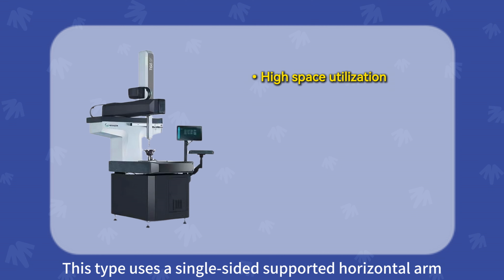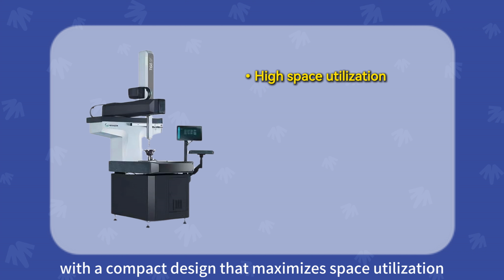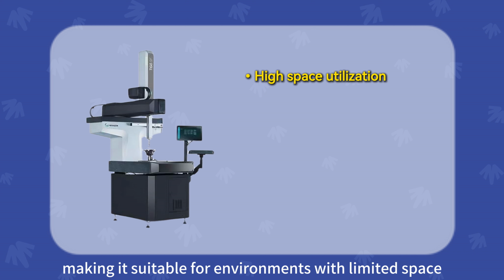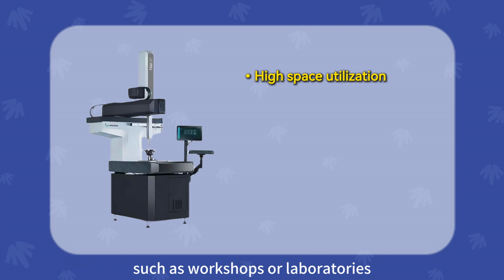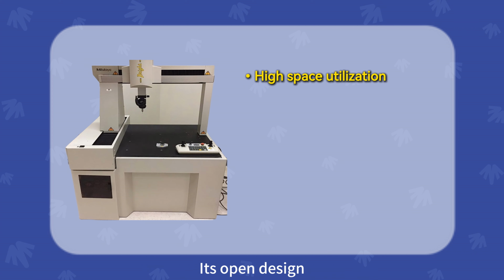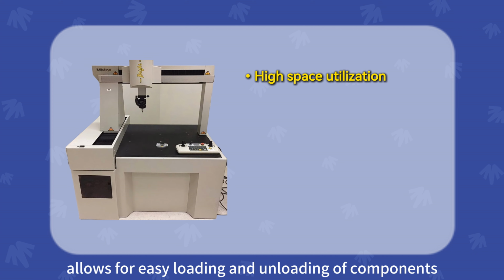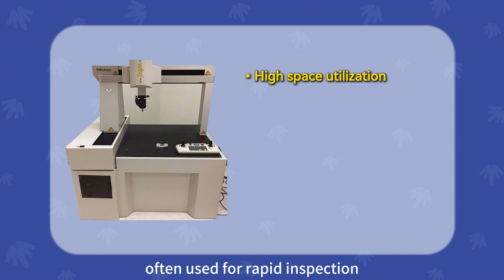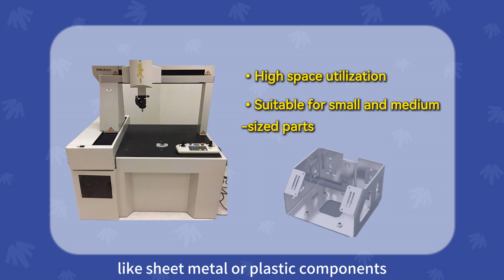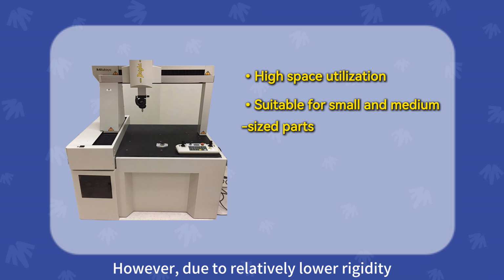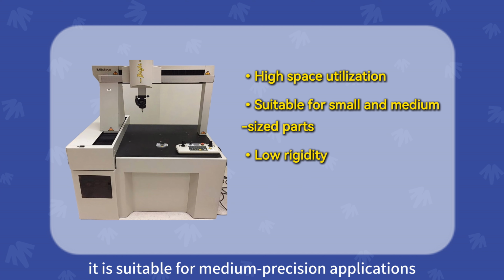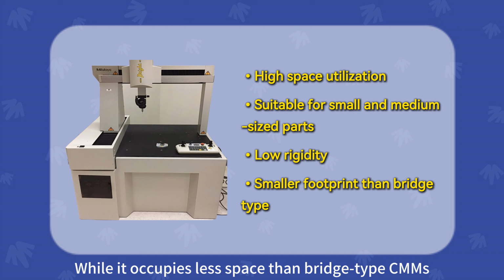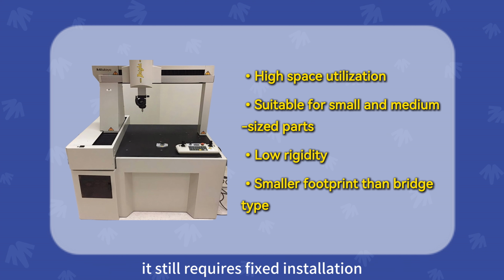Cantilever-Type CMM. This type uses a single-sided supported horizontal arm, with a compact design that maximizes space utilization, making it suitable for environments with limited space, such as workshops or laboratories. Its open design allows for easy loading and unloading of components, often used for rapid inspection of small to medium-sized parts like sheet metal or plastic components. However, due to relatively lower rigidity, it is suitable for medium precision applications. While it occupies less space than Bridge-Type CMMs, it still requires fixed installation and is not easily movable.